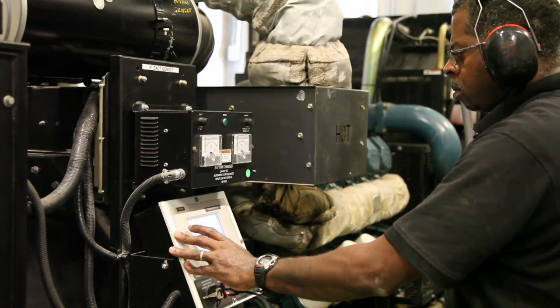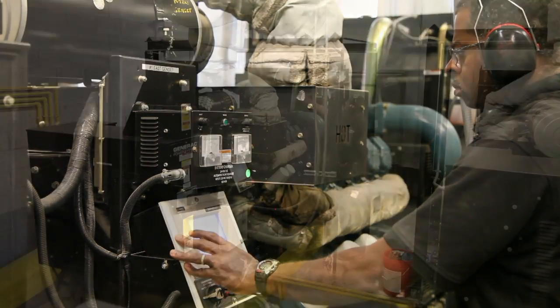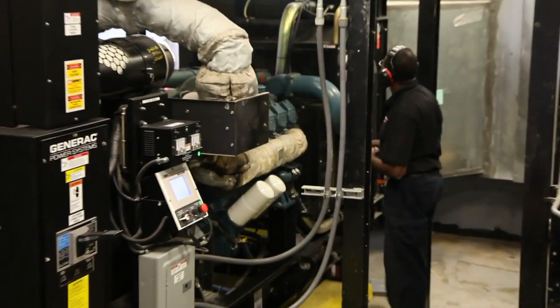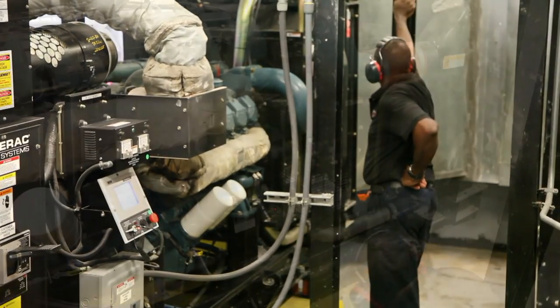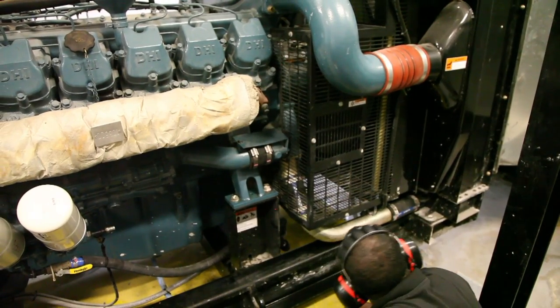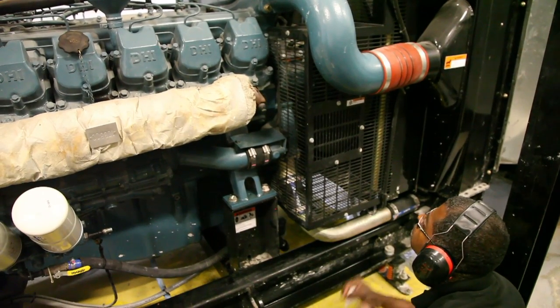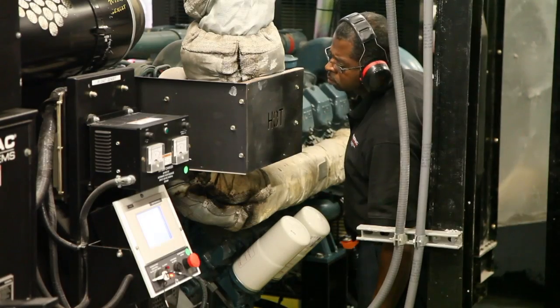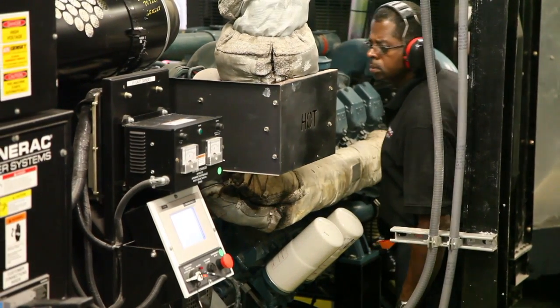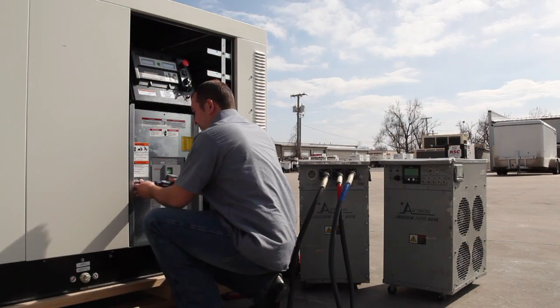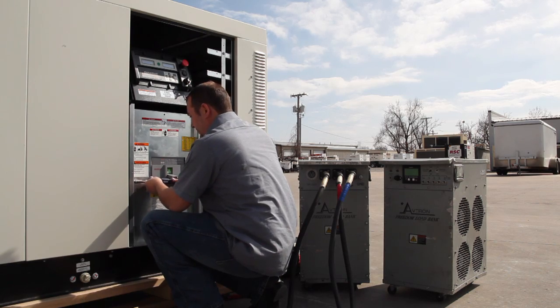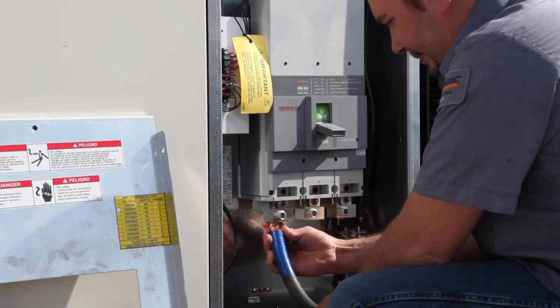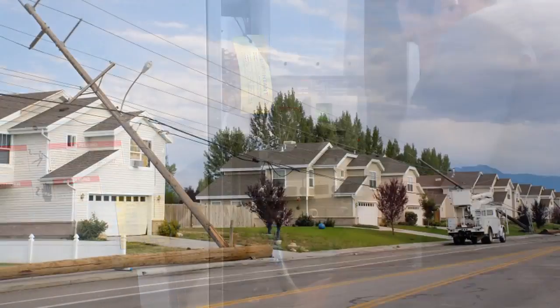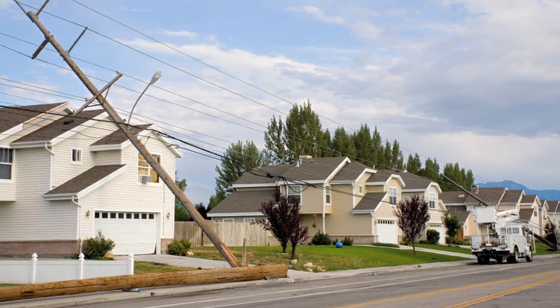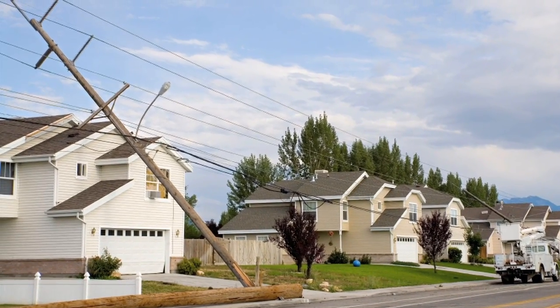While running, the technician will check all the gauges and switches. Hot leaks detect issues when the coolant is hot and circulating under pressure. The technician will check for any radiator and hose leaks inside and outside the canopy while the generator is running. The technician shuts down the generator and further examines for leaks after the hot leak test is completed. To ensure proper operation for prolonged periods at operating temperature, we recommend a full load bank test. Make sure your generator system remains cool when called upon in an emergency.